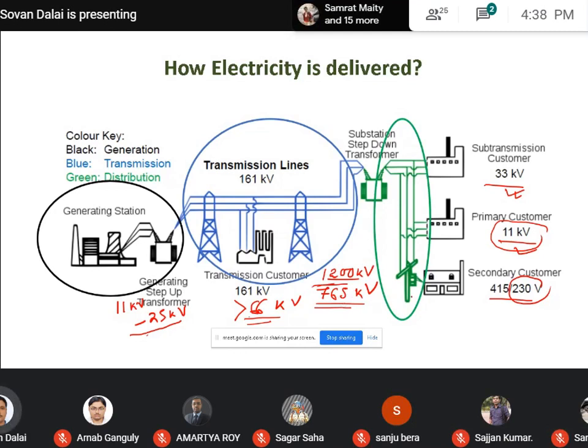And the distribution voltage level differs according to customer needs. As domestic consumers, we consume 230 volt, and mind that this voltage is single phase. All the other voltage levels are three-phase. Only as domestic consumers do we consume single-phase 230 volt, and some factories use three-phase voltage in the range of 415 volt. Primary and secondary customers are comparatively bulk consumers compared to domestic customers. They consume power at higher voltage levels in the range of 11 kV and 33 kV.